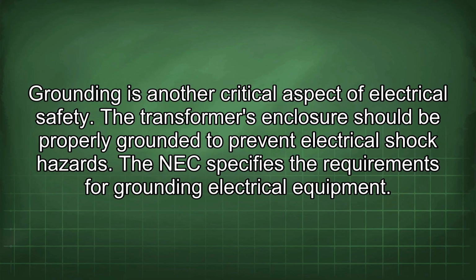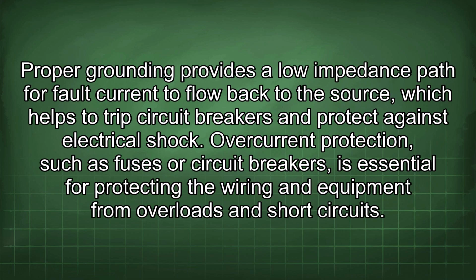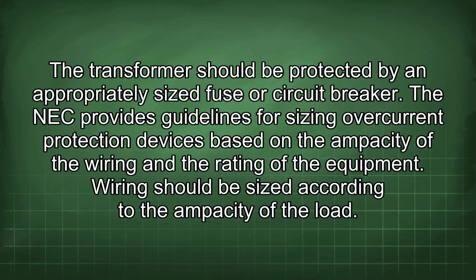Grounding is another critical aspect of electrical safety. Transformers and enclosures should be properly grounded to prevent electrical shock hazards. The NEC specifies the requirements for grounding electrical equipment. Proper grounding provides a low impedance path for fault current to flow back to the source, which helps to trip circuit breakers and protect against electrical shock. Overcurrent protection, such as fuses or circuit breakers, is essential for protecting the wiring and equipment from overloads and short circuits. The transformer should be protected by an appropriately sized fuse or circuit breaker.